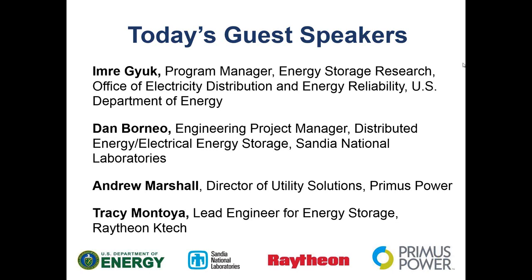This is Dan Borneo. Tracy, how long does it take your system to go from charge to discharge? On the RK10 system we've been testing at Sandia, it takes about four hours for a full charge cycle and about three hours for a full discharge cycle. My next question is: if you're charging and something happens and you need to go to discharge to back up a load, how fast can it make that transition? It's within 30 seconds.